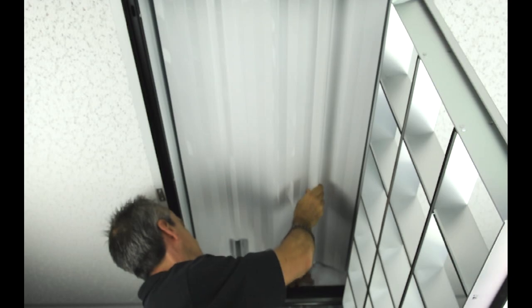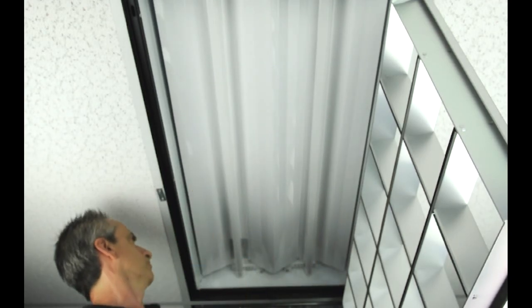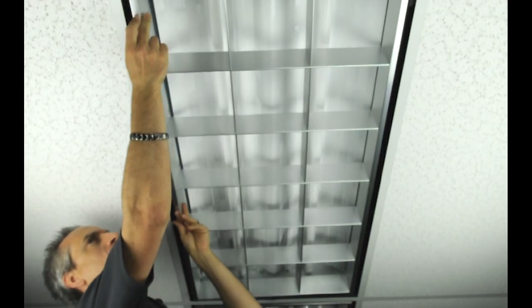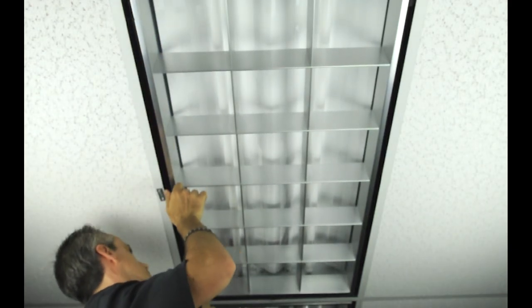Install the lamps and turn the power back on. Remember, you must use ballast bypass lamps for any future lamp replacements, but no additional fixture rewiring is required.